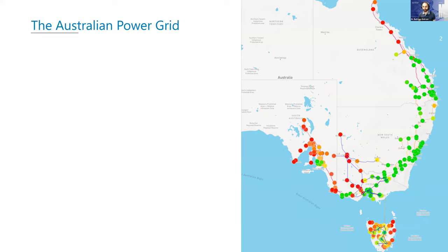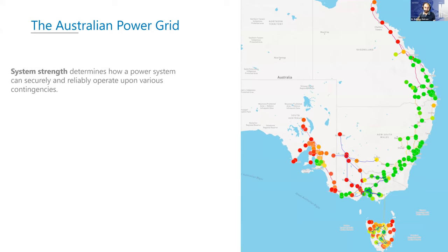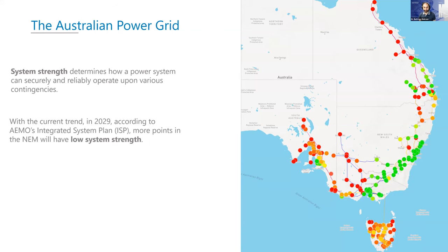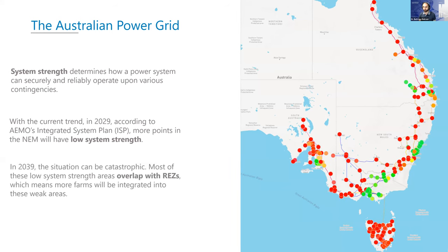This is the Australian power grid — at least the NEM, the National Electricity Market — and the dots represent system strength. Greener means better system strength, which determines how reliably your power system can operate upon different contingencies — how well it can recover from a fault. When you have very low system strength, it's difficult to recover after a fault and your farm might get disconnected. As projected by AEMO's ISP, the situation could be even worse in 2029 and worse still in 2039. We need to do something, particularly because renewable energy zones are mostly overlapping the red dots, meaning we cannot comfortably and reliably integrate more renewables.